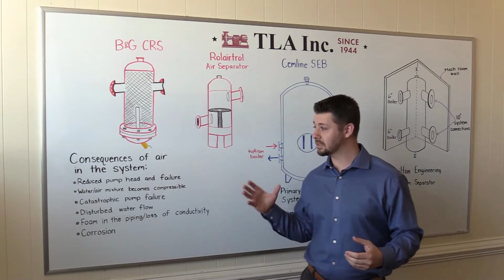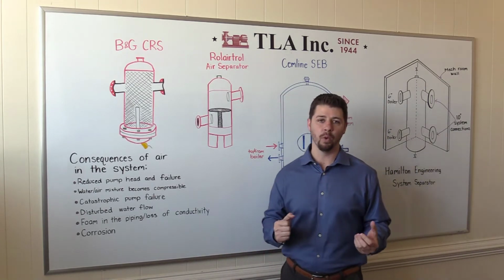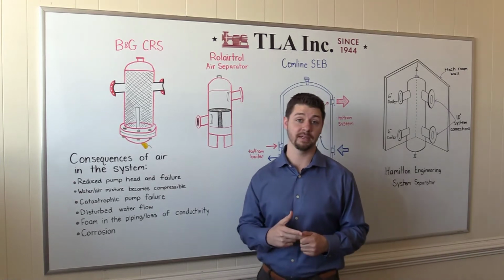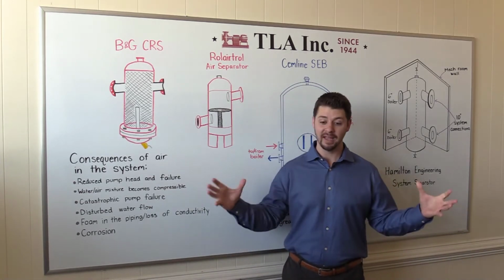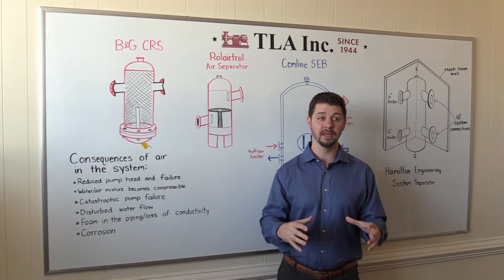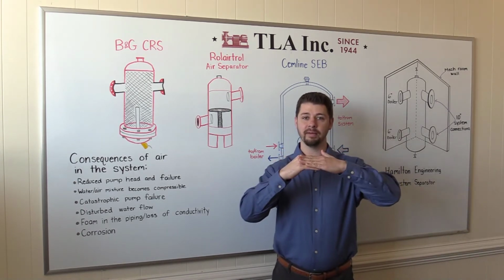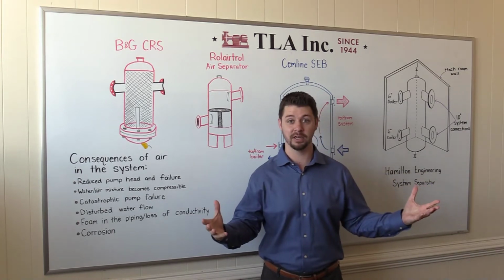So in a hydronic system, having air in the water can cause pump cavitation amongst a number of other things, and especially in boiler systems, if air gets into our boilers and that becomes our slow spot of the system, we can start having flame to metal contact and break heat exchangers.